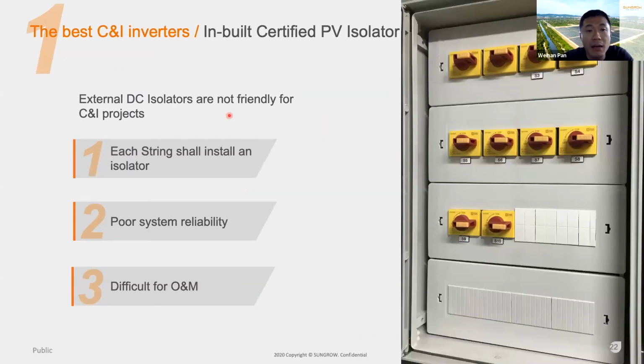And in the following, I will give some general ideas and address the advantages of our inverter. As Scott mentioned, not only the residential inverter, but also all of our inverter products, especially the C&I ones, have an inbuilt certified DC isolator. On the right side of my slide, you can see the traditional DC combiner box with a lot of DC isolators, because according to the regulation, you have to install an extra isolator next to the inverter. As a result, there is poor system reliability, because each extra DC isolator means one more failure point in the system. As well, for operation and maintenance, so many DC isolators might be difficult to maintain and operate.